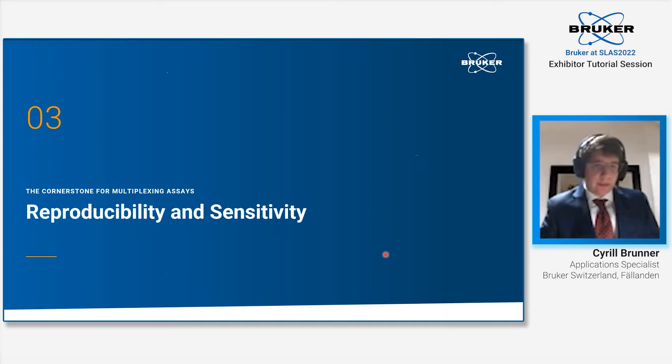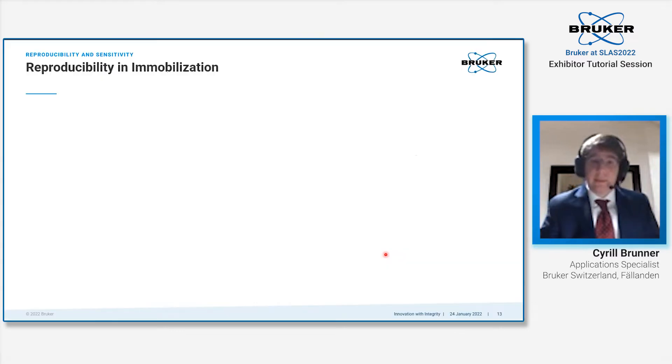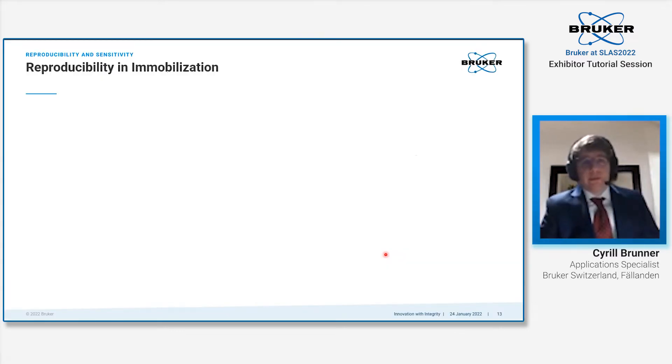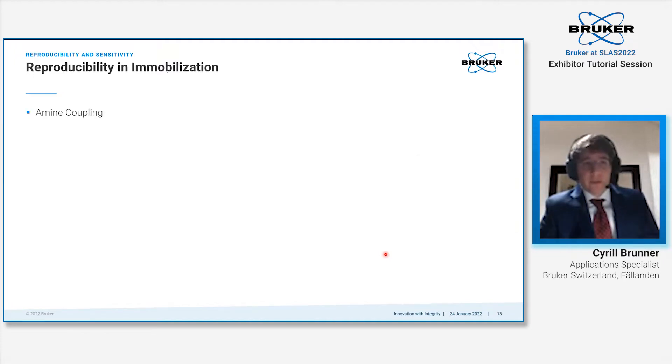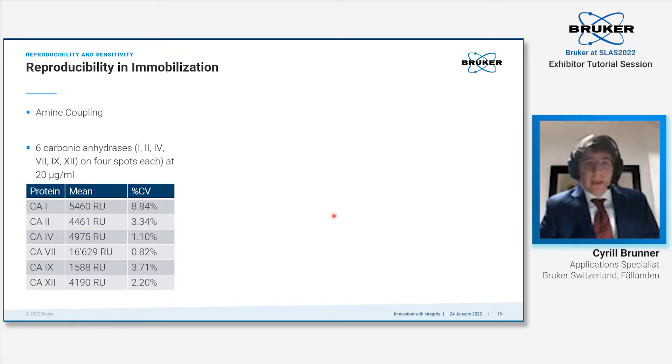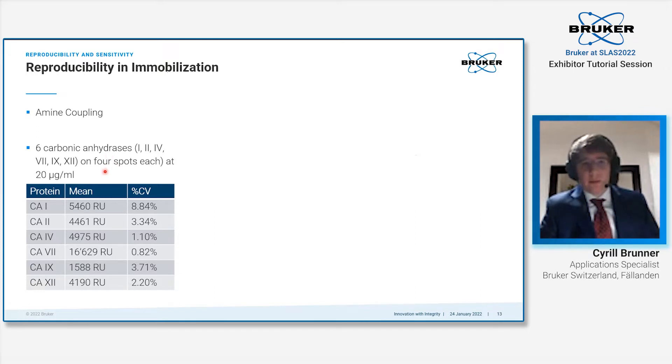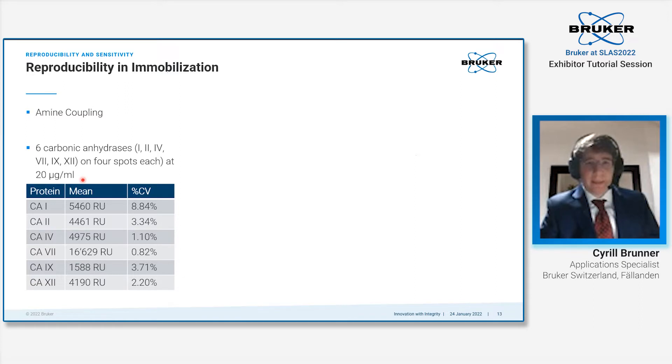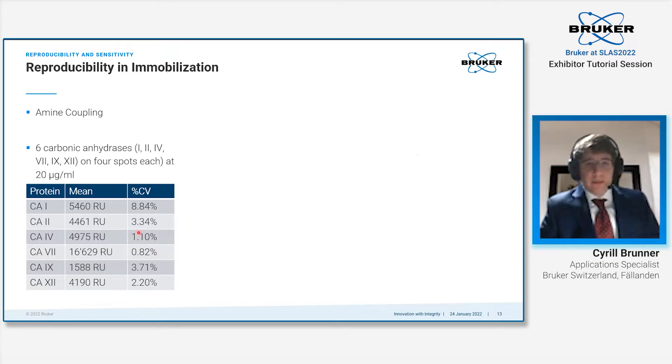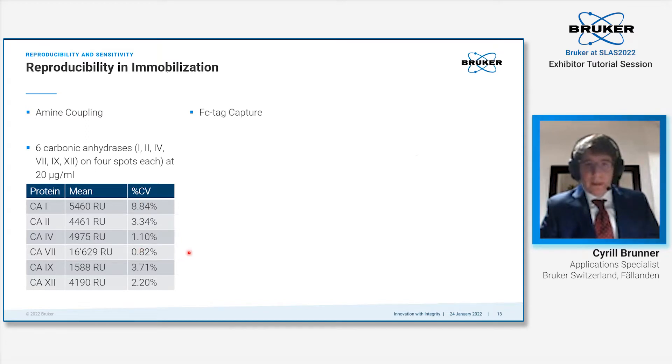An important aspect of any SPR system is reproducibility and sensitivity. We first looked into the reproducibility of our system with immobilizations. The first example is amine coupling. We used six carbonic anhydrases with each carbonic anhydrase being immobilized on four sensor spots at 20 micrograms per ml. We are below 4% CV with the exception of carbonic anhydrase 1, but still below 10% for all.